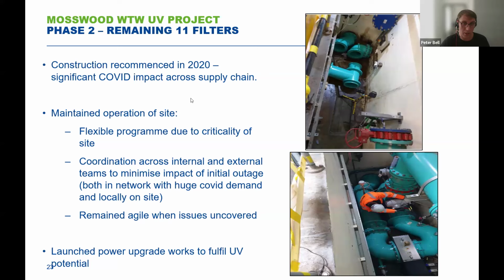Alongside that, as part of this program, we also launched the power upgrade works to fulfill the UV potential. When we initially installed the UV, we recognised, as part of the design, that we wouldn't be able to run the UV reactors at full power if we needed to. Just to give a bit of context, they on average run around 25 kilowatts. They can go up to 50 kilowatts. So we proceeded with a project to upgrade the works power. That involved a new main supply from our electricity network and also the installation of a new site generator, which was then able to power all of the UV at 100%.